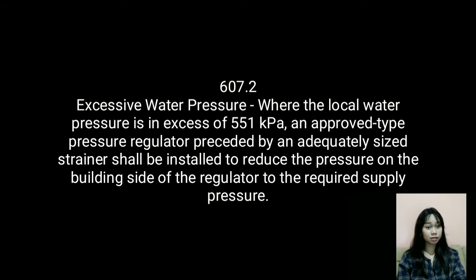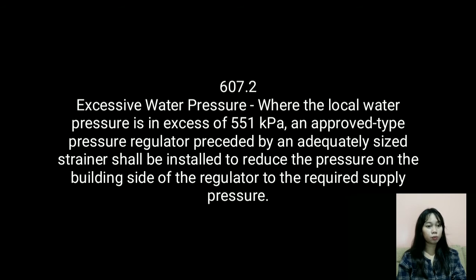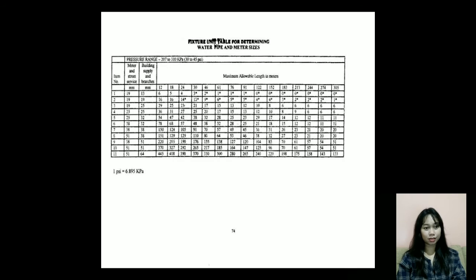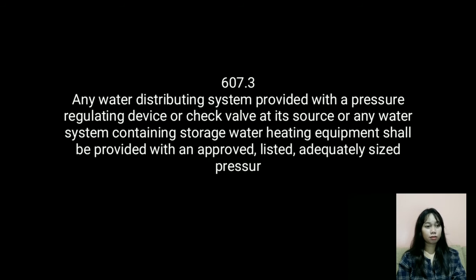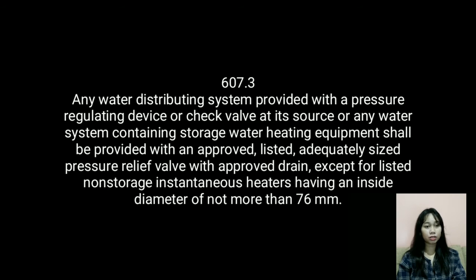Section 607.2 addresses excessive water pressure. Where the local water pressure is in excess of 551 kilopascals, an approved type pressure regulator preceded by an adequately sized strainer shall be installed to reduce the pressure on the building side of the regulator to the required supply pressure. Approved regulators with integral bypasses are acceptable. Each such regulator and strainer shall be accessibly located with the strainer readily accessible for cleaning without removing the regulator body or disconnecting the supply piping. All pipe size determination shall be based on 80 percent of the reduced pressure when using Table 6-6.